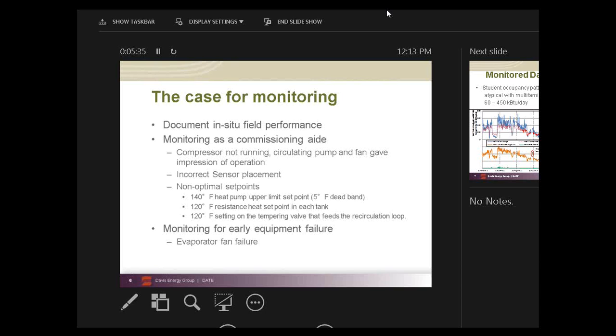Another issue that was noticed was the temperature feedback for the heat pump was low, and it was determined that a sensor was improperly installed in the tank. So we had them fix that during the first monitoring phase. And then the manufacturer supplied recommended temperature settings for the operation to make more use of the heat pump water heater. But we noticed during monitoring that the heat pump cycles were short and frequent, and we suggested different points in order to optimize and extend full load operation. But during this monitoring period, we decided to continue with the manufacturer's recommended settings, and that's reflected in the data that's reported.